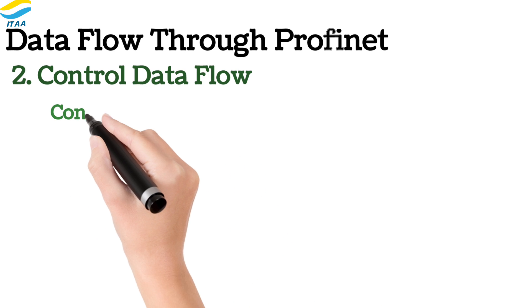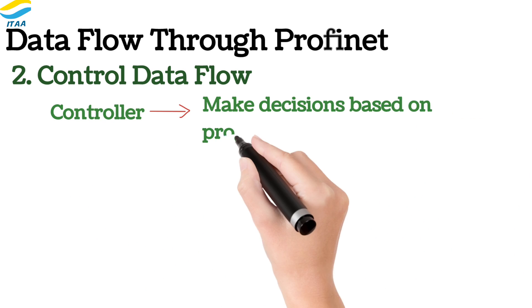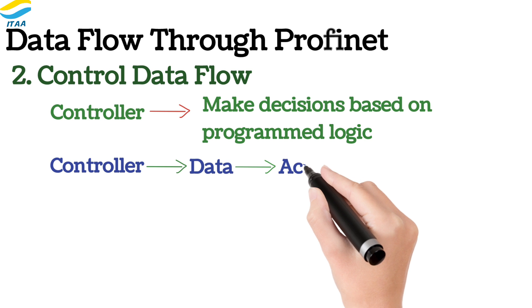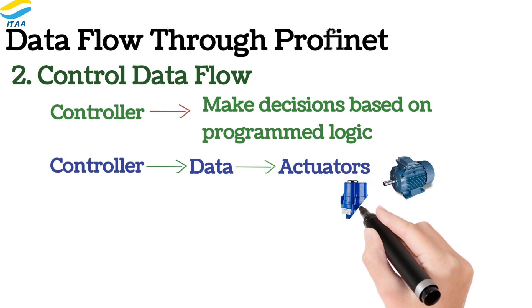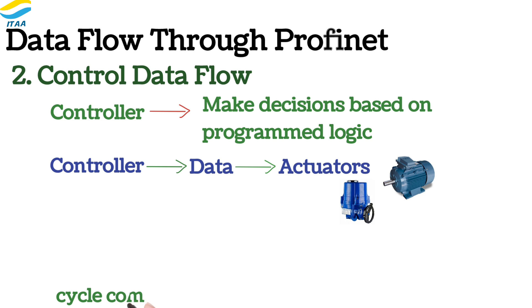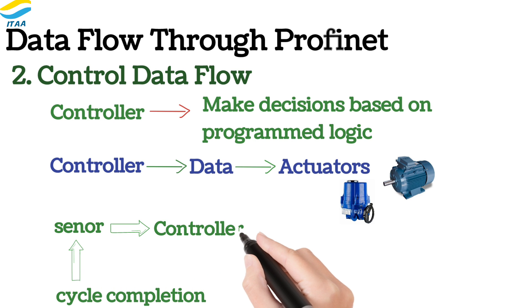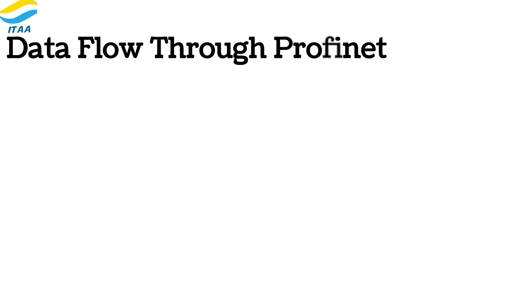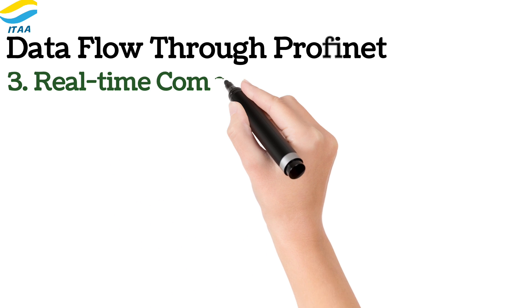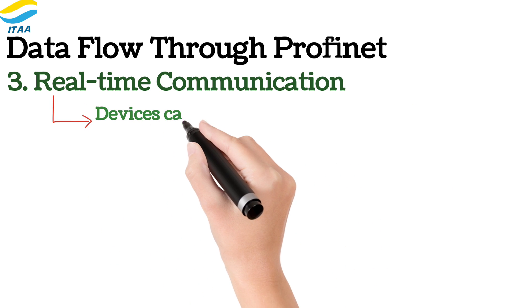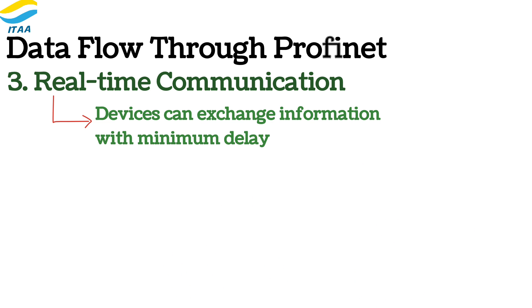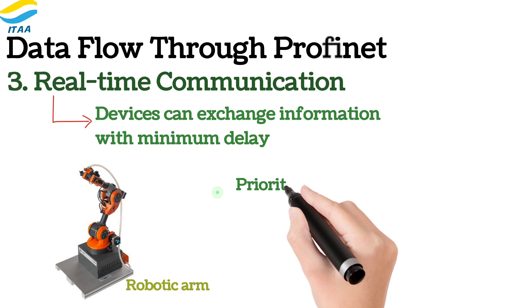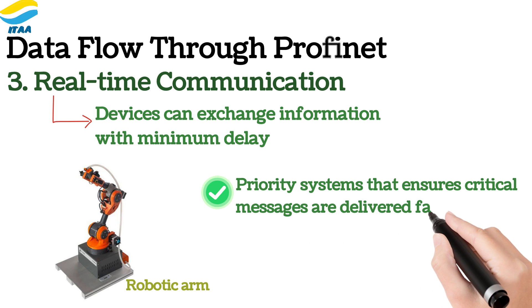Once the controller receives sensor data, it processes this information to make decisions based on the programmed logic. The control data generated by the controller is then sent to actuators or output devices. Actuators could be motors, valves, or other machinery responsible for physically carrying out commands. For example, if a sensor detects that a machine part has completed its cycle, the controller can send a command to the motor to either start a new cycle or stop the machine. One of the key strengths of PROFINET is its ability to handle real-time communication, meaning devices can exchange information with minimal delay — critical in processes requiring synchronization such as motion control or robotics. PROFINET uses a priority system that ensures critical messages are delivered faster than non-essential data.